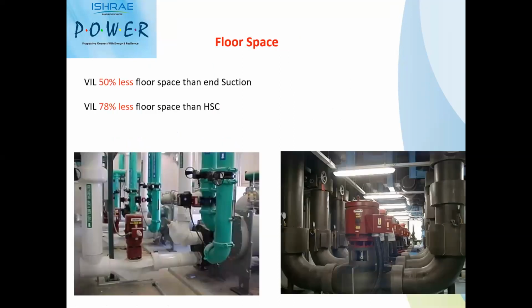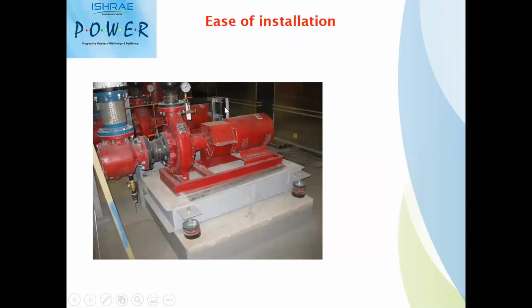This is a typical pump arrangement where vertical inline pumps are installed in the chiller section, or the pumps are installed at the back, with very little space. As a general calculation from our experience in the market, vertical inline saves 50% space compared to end suction pumps and 78% space compared to horizontal split case pumps.